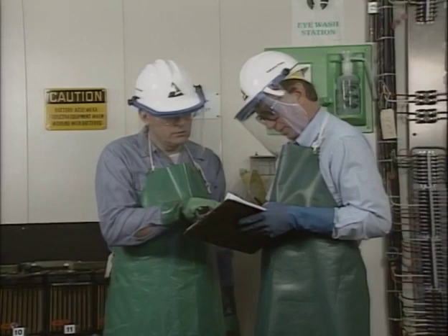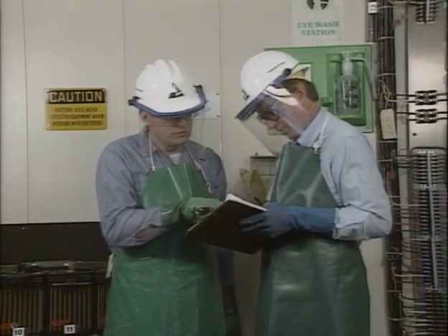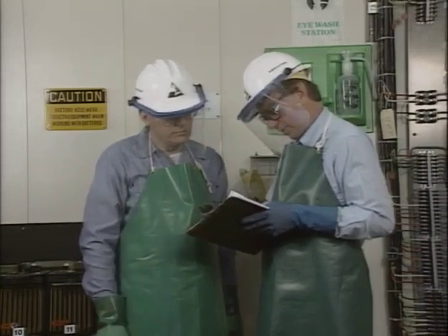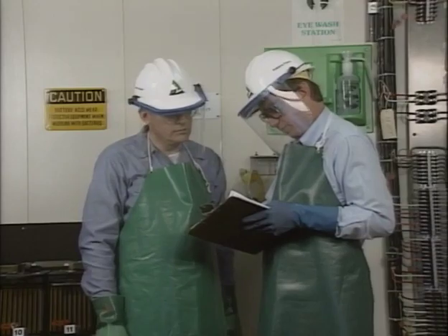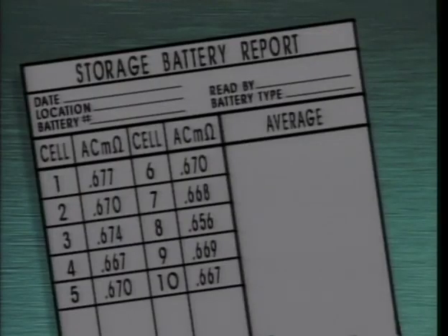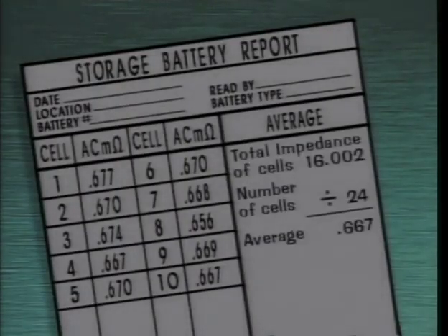The impedance measurements can be interpreted for individual cell condition and for remaining cell life expectancy. To evaluate cell condition, the cell impedances for the entire battery are averaged. Then the individual cell impedances are compared with the average. If cell impedances vary by more than plus or minus 20% from the average, the battery may need to be put on an equalizing charge, or the questionable cells may need to be capacity tested.